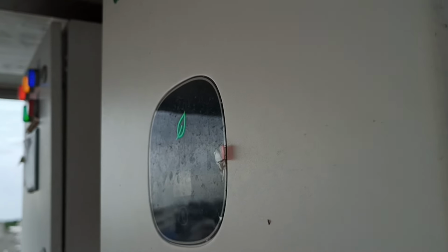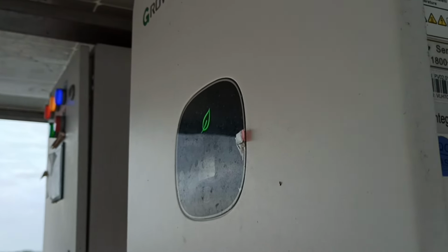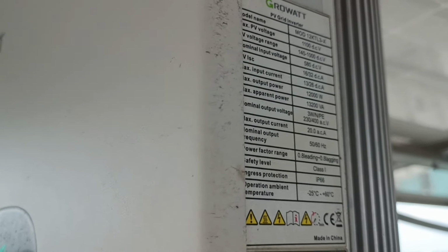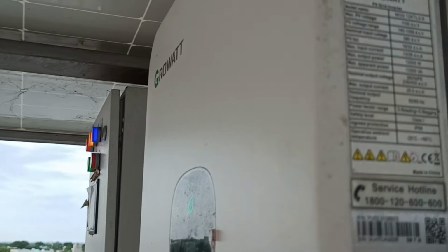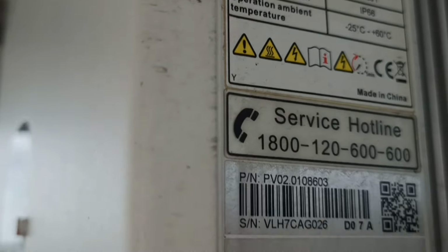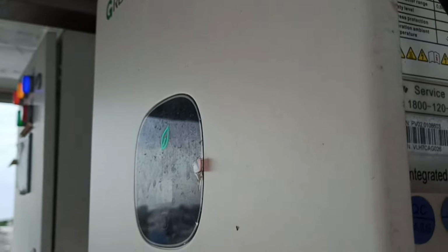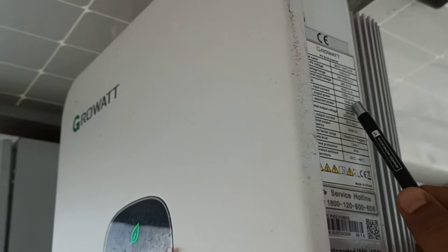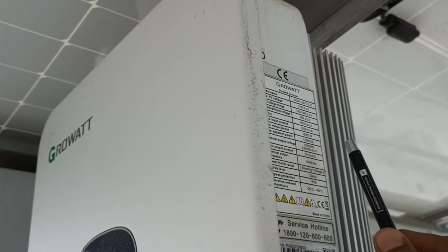So resultantly this is nothing but 13 kilowatts. For the solar PV voltage, the maximum input voltage you can apply is up to 1100 volts, and we are applying 580 volts DC from the series connection, which is also the nominal input voltage. Coming to the current, the PV ISC, the PV short circuit current, is 16 amperes. The maximum output power it can deliver is 12 kilowatt or 13.2 kVA.